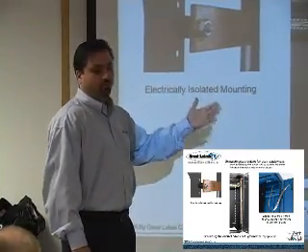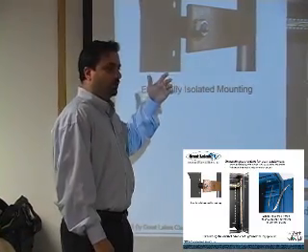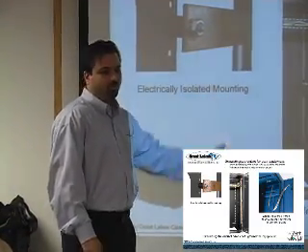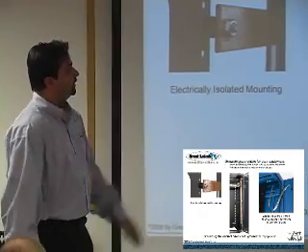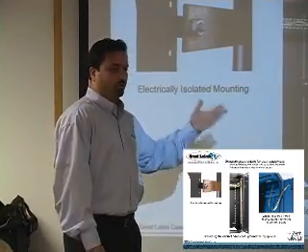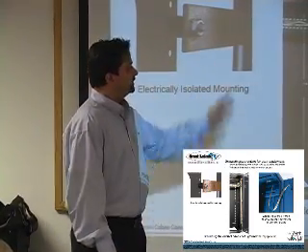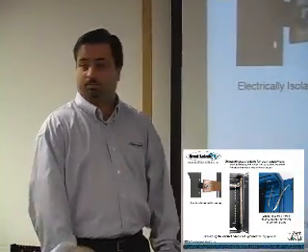That way it's a positive ground. You're certain that the equipment is grounded rather than hoping that it's grounded to the cabinet, and that the cabinet is grounded. It's not always a good connection that way. And then also ground every panel within the enclosure, making sure doors, sides, tops, bottoms, whatever, are all connected to a common ground, and then going out of the facility from there.